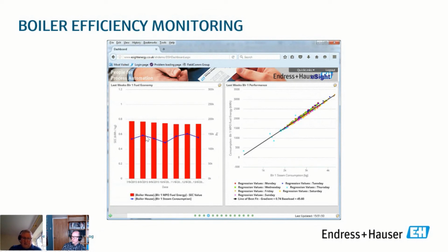This blue line is just the steam load on the boiler. So you'd expect whenever you've got the highest loading on that boiler, you'd probably have one of the better ratios of fuel economy. This other graph here is graphing the steam consumption on this axis against the fuel on this axis.